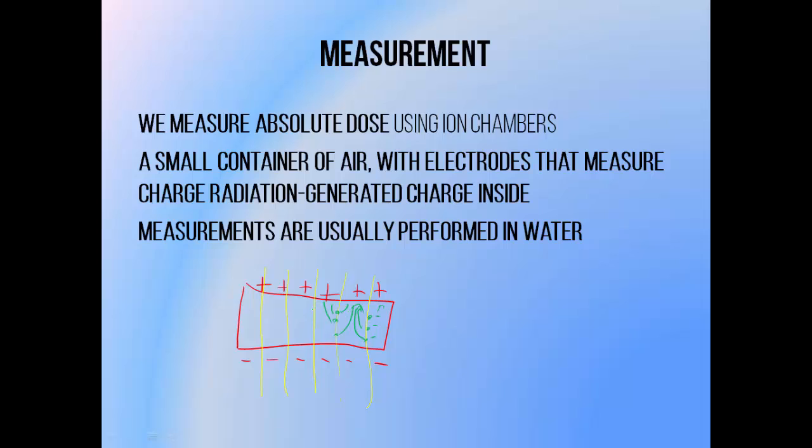Putting a voltage across the chamber causes one wall or electrode to become positive and the other to become negative. The negative charges tend to move towards the positive end, and positive charges tend to move towards the negative. We can measure the amount of charge reaching these walls or electrodes using an electrometer, which would connect to the ionization chamber.